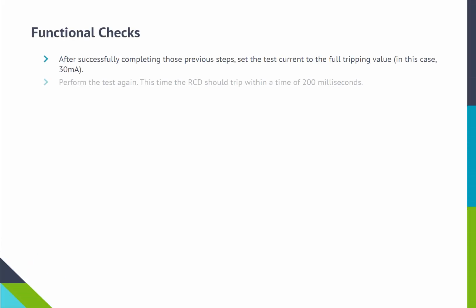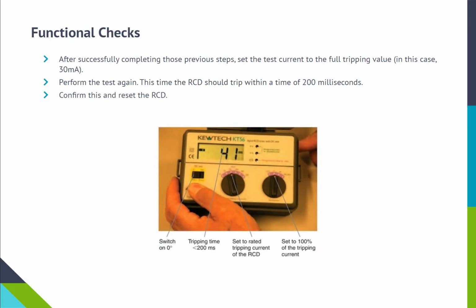After successfully completing those previous steps, set the test current to the full tripping value, in this case, 30 mA. Perform the test again. This time the RCD should trip within a time of 200 milliseconds. Confirm this and reset the RCD.